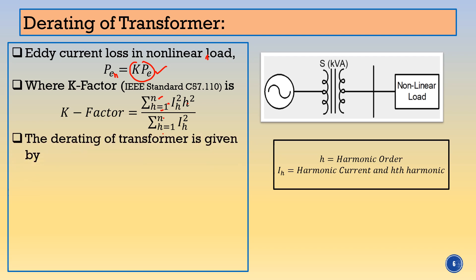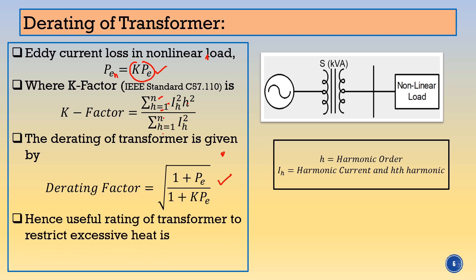The derating factor is calculated from the eddy current loss, because it is going to impact eddy current loss. The derating factor = √[(1 + PE) / (1 + K·PE)]. Hence the useful rating of the transformer is restricted. S_useful = derating factor × S, where S is the rating of the transformer.